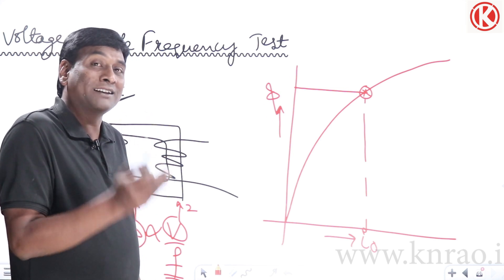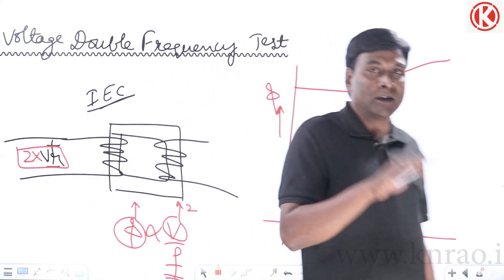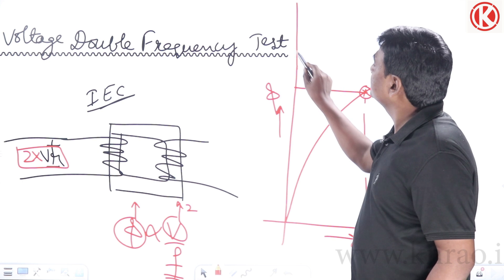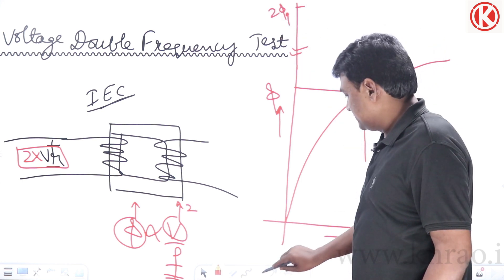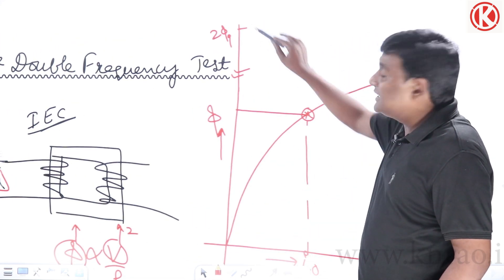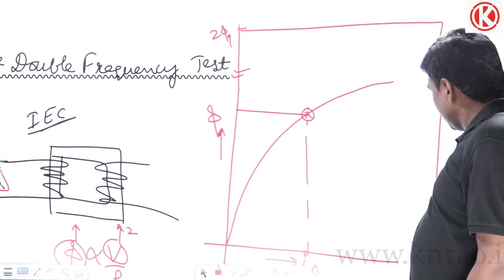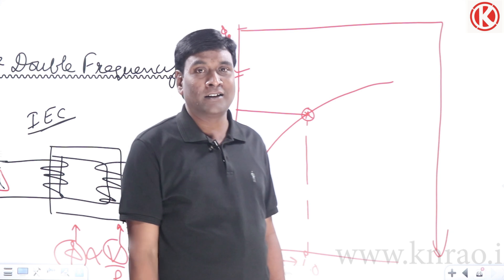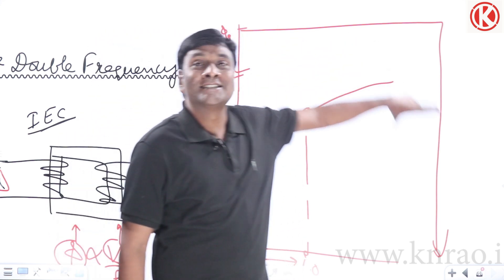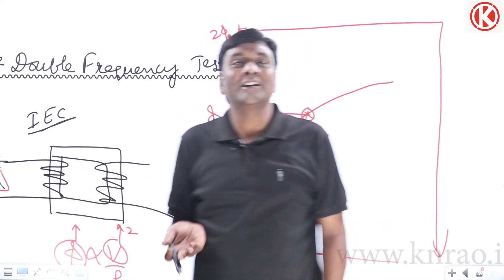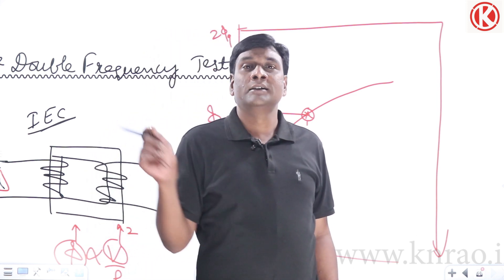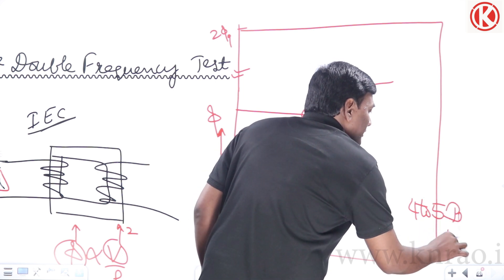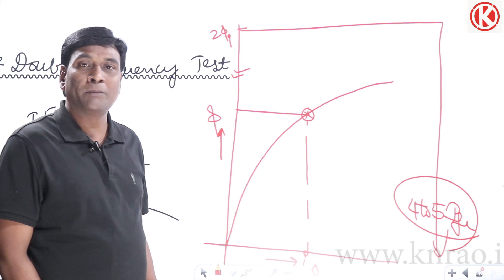If the operating flux is doubled, we know from magnetic inrush analysis that flux can double depending on the time of switch closure. If the normal operating flux is at B-max, doubling it gives 2×B-max — deep into saturation. At that doubled operating flux, the no-load current can become four to five times the full load current. Unlike magnetic inrush which is transient, this would be a steady-state condition during the test, which would surely burn the windings.